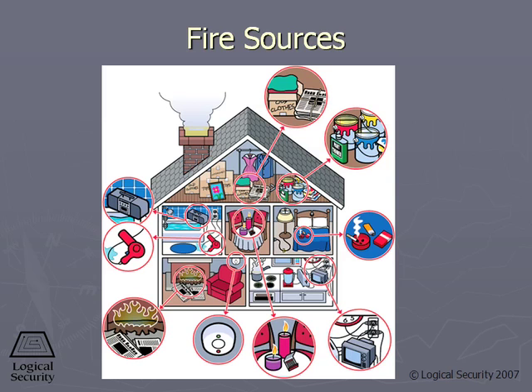The suppressants we use to put out the fire will affect one or more of these four legs of the fire. You should know all four of them. Our fire prevention measures will either reduce the temperature, remove the fuel, disrupt the chemical reaction, or remove the oxygen from the source of the fire. The sources of fires are all over, and you should, during your physical inspection of the facilities, recognize and identify these fire sources so that you have proper countermeasures in place.